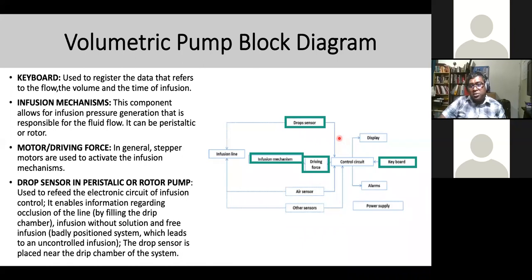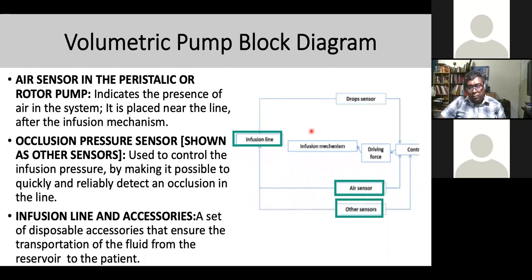Drop sensor is used in peristaltic type and rotor pump. So drop sensor is to monitor the infusion line fluid drops going into the system, and it calculates how many drops, in liters or milliliters, have been used. So all the information will be sent to the control board. Air sensor, for peristaltic or rotor, indicates air in the line. This is important because you don't want air inside the infusion line.